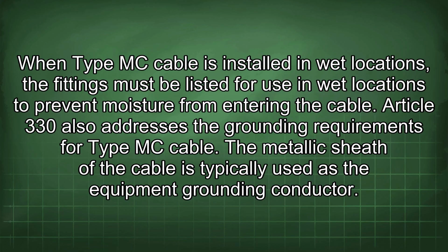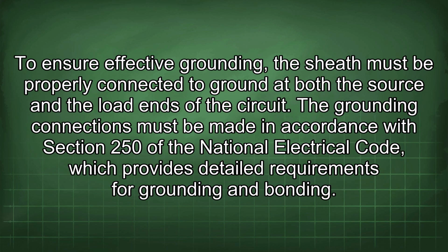Article 330 also addresses the grounding requirements for Type MC cable. The metallic sheath of the cable is typically used as the equipment grounding conductor. To ensure effective grounding, the sheath must be properly connected to ground at both the source and the load ends of the circuit. The grounding connections must be made in accordance with Section 250 of the National Electrical Code, which provides detailed requirements for grounding and bonding.